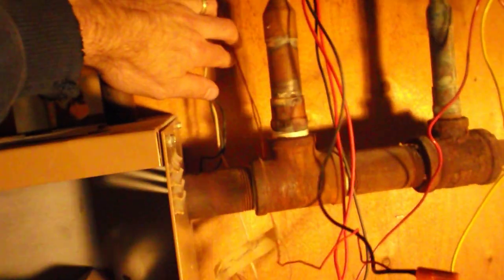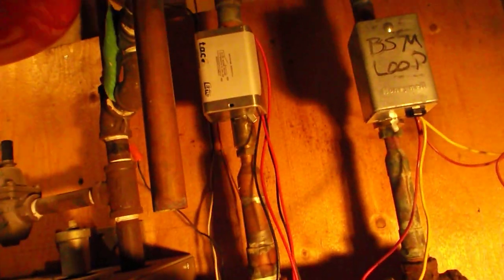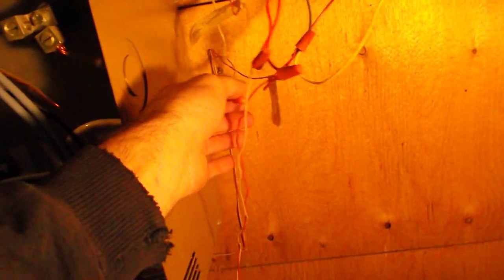This pair of wires comes from the thermostat, so it's just a very thin pair of copper wires. When the thermostat is off, those wires have an open circuit at the end. But when the thermostat is on, in other words, sending the signal to turn on the heater, that pair of wires is a short circuit. One of the wires runs up to the zone control and one of the wires runs down to the transformer.